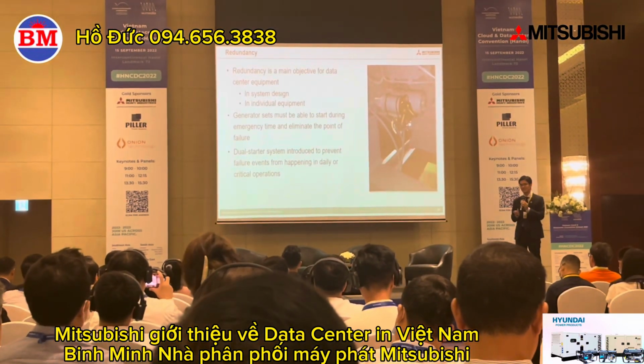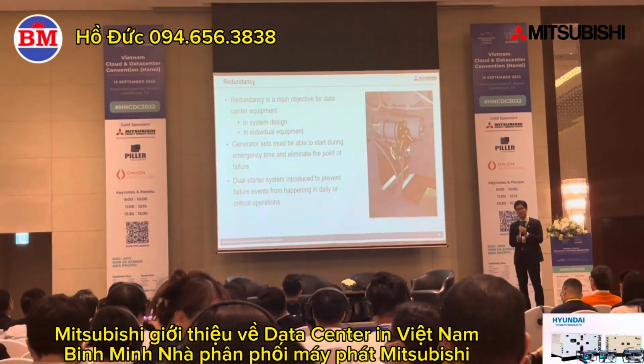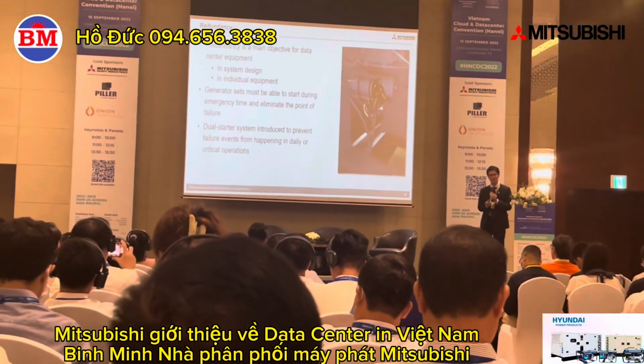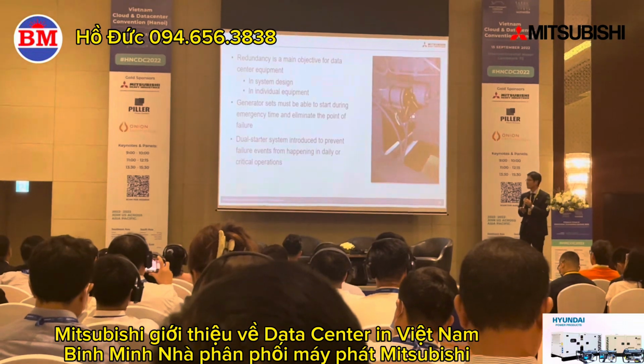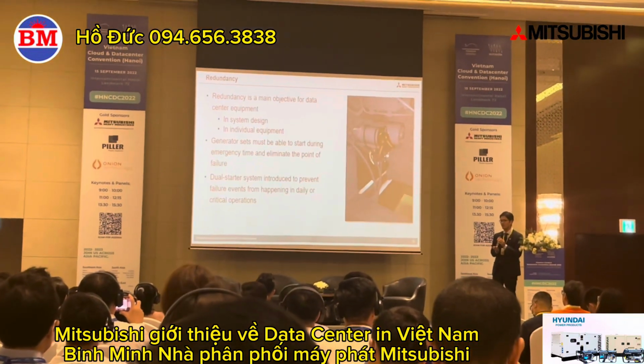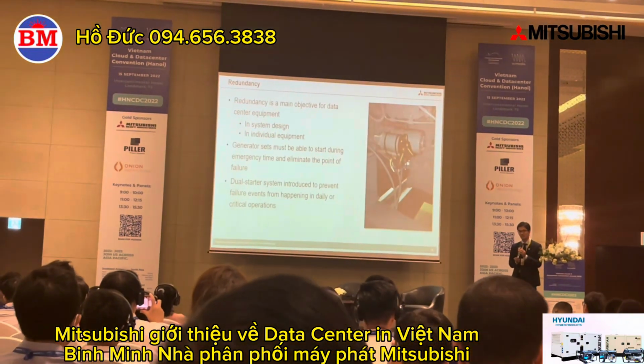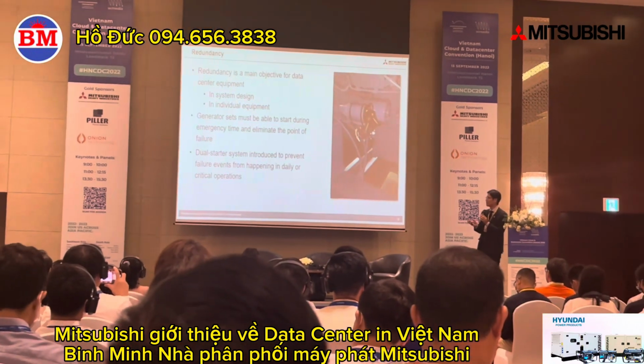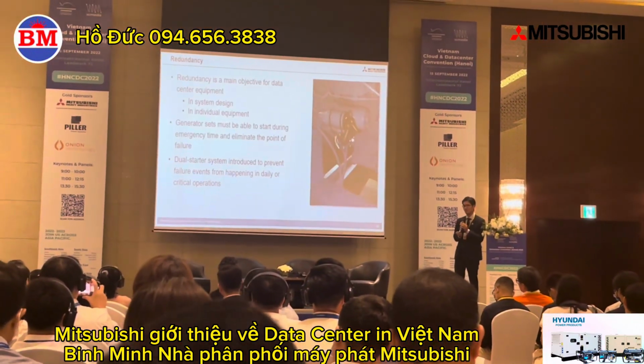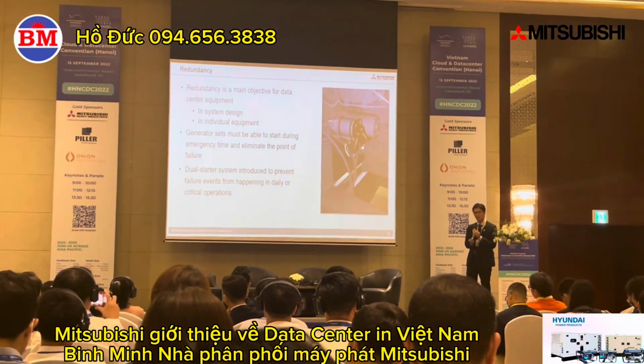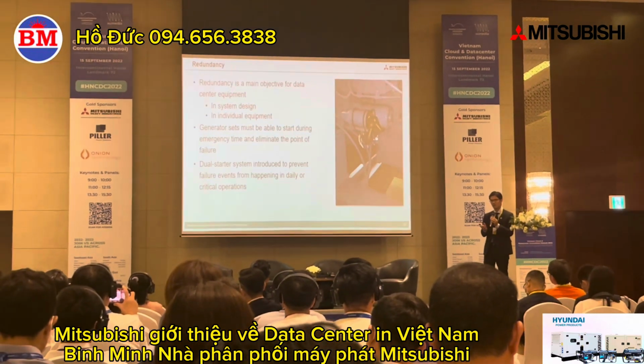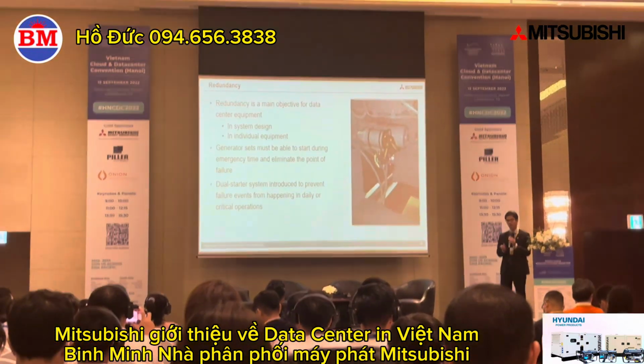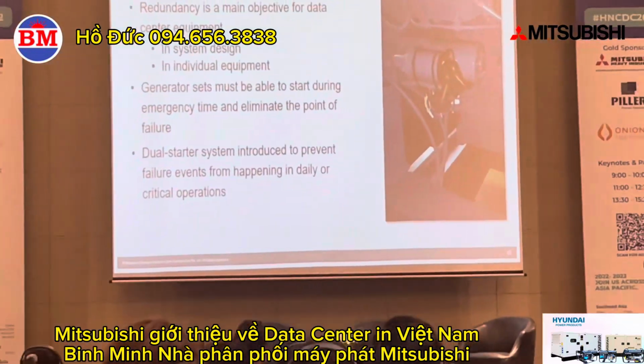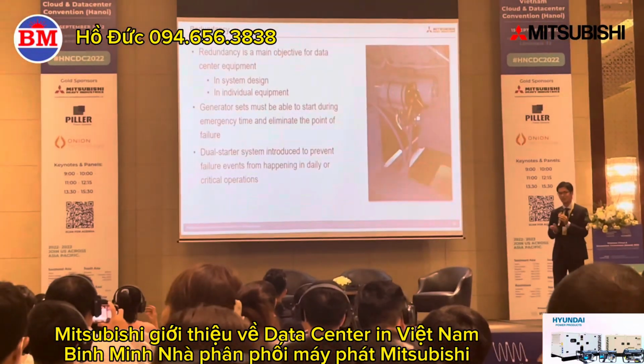So for the generator set, the starting process is one of the most important processes. In this sense, there are customers who require redundancy in the starting process, and we have implemented this dual starter system since 2020. For now, most customers require this dual starter system because they want to have redundancy in the starting and cranking process.